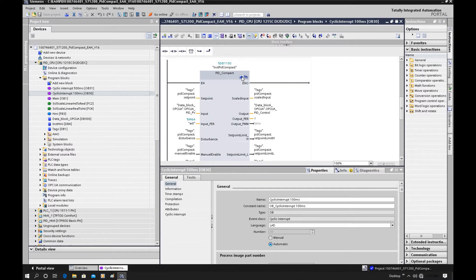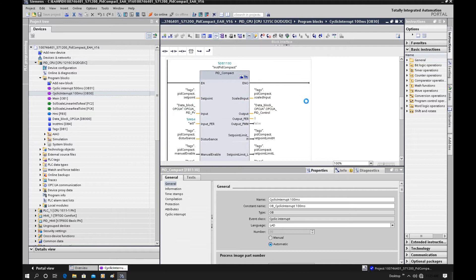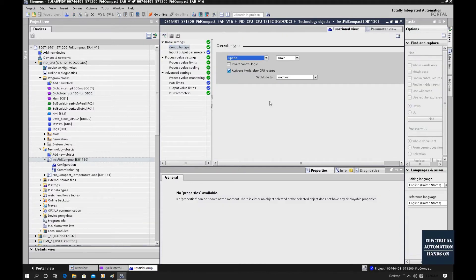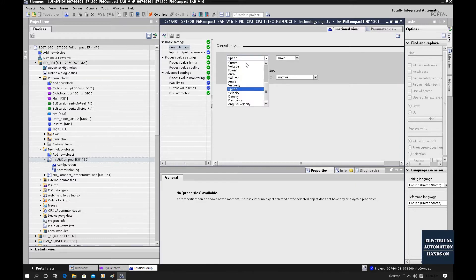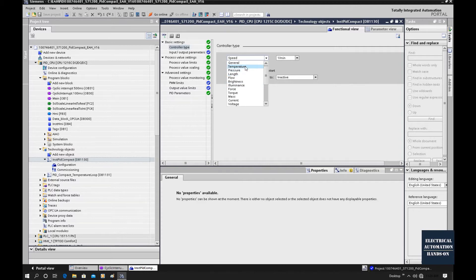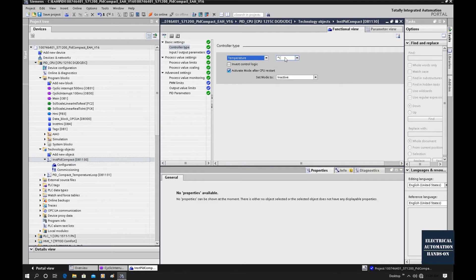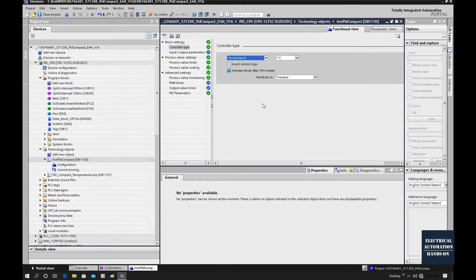Let's click this configuration button to look at the detail configuration inside this PID loop. Because our process is a temperature system, and that is a cooling system, I will select this as a temperature loop. This selection is just a name used to adjust this unit here. Regarding this invert logic, in my case, I need to select this to invert the logic. That means our gain will be a minus value.